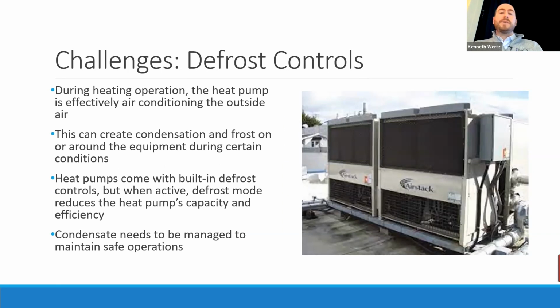Along those same lines on cold weather operation, this one is just something to be aware of. When it's cold outside and you're heating the building from a heat pump, you're effectively air conditioning the outside air. So you're making it colder around the unit, which can cause frost to build up on it. And that's a maintenance concern, something you want to be aware of. The units have built-in defrost controls, but it's not always perfect. And when that defrost goes into effect, the unit's not performing the way it otherwise could. So you may have to put in more capacity to anticipate that condition, or else have that alternative system you could switch over to if need be, if the heat pump's not keeping up.